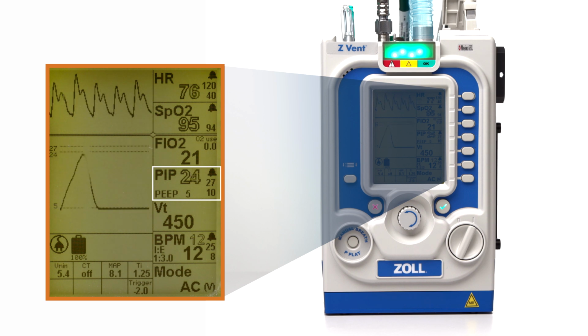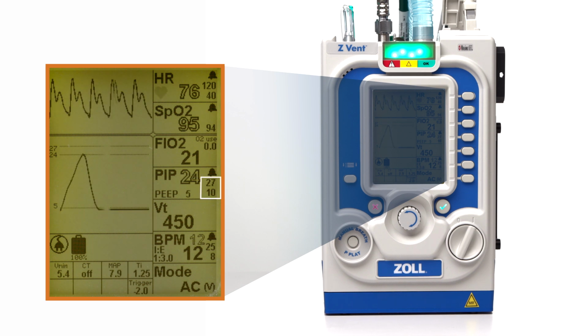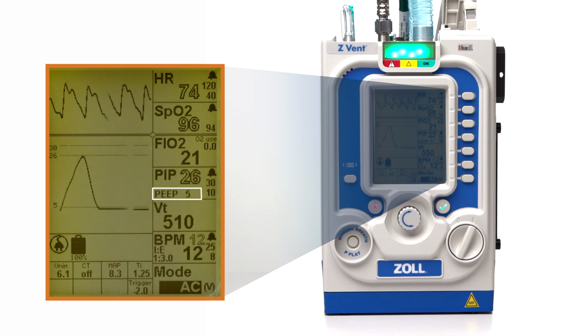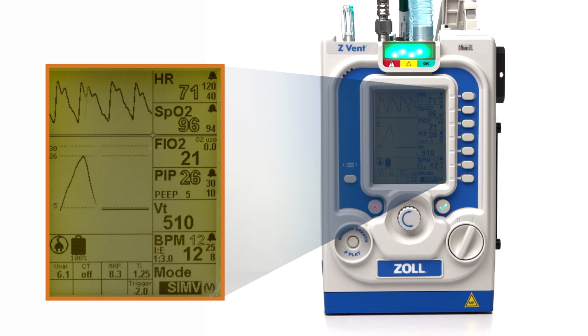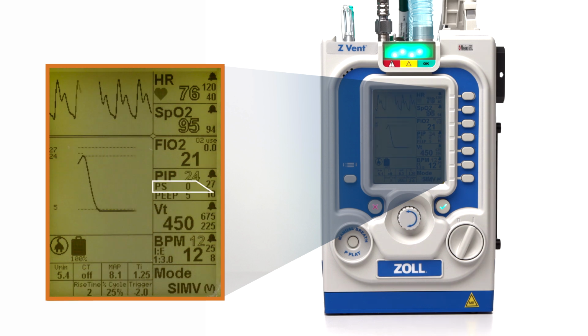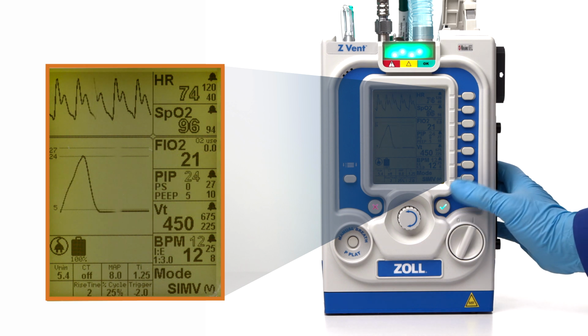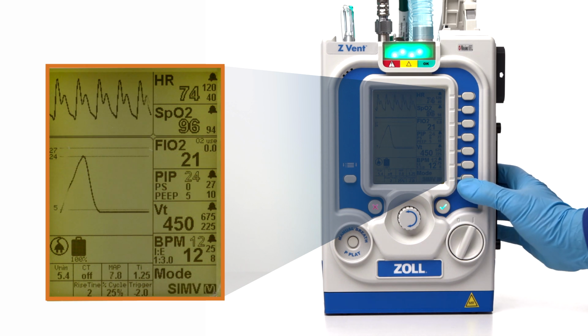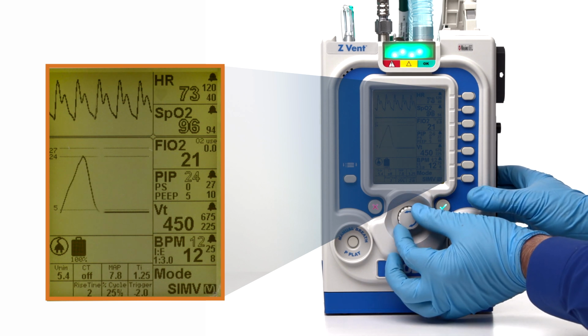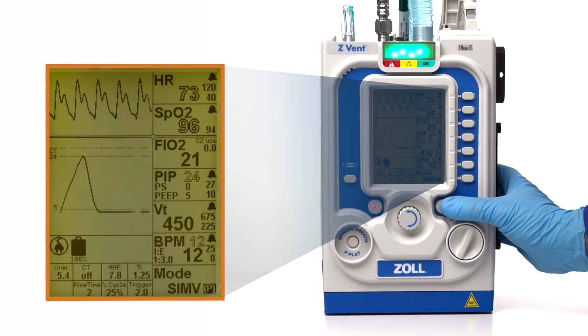Airway pressure settings are also changed from this window. This window displays the current PIP value, high pressure limit and low pressure limit alarms, and the current PEEP setting. When operating the ventilator in SIMV, CPAP, or BL modes, pressure support will be displayed as a secondary parameter that can be adjusted. When operating in a pressure-targeted breathing mode, PIP is a solid numerical value and can be changed.